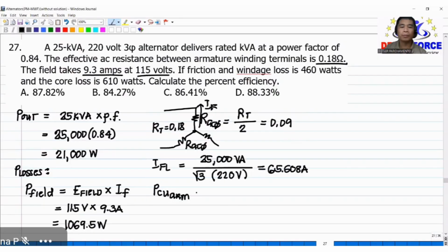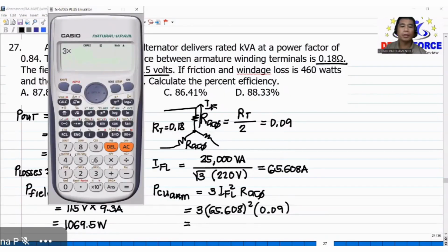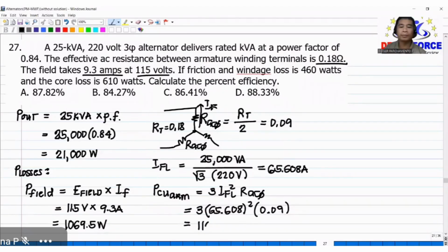at the armature, so 3 phase, so 3 times I full load squared times RAC per phase. 3 times the full load current, 65.608 squared times RAC, 0.09, equivalent to, so 3 times 65.608 squared times 0.09, 1162.191 watts. So therefore, what is the efficiency?